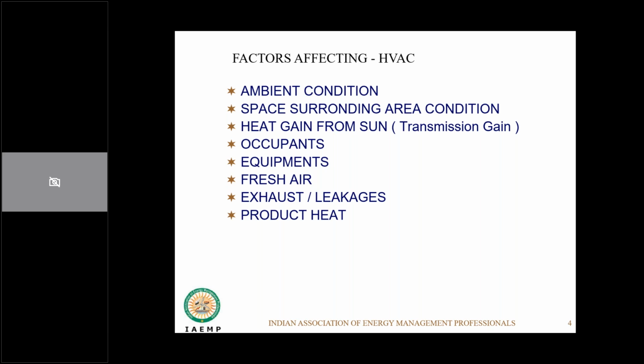This is also very important when you're doing cold storage, because if you have a product which is germinating, it generates a lot of heat, and you need to factor that in and maintain the right temperature in your cold storage. If you look into the cold storage of potato and onion, it's a very important factor, because if the temperatures go up, onion and potatoes start germinating, and then the product is lost and you have to throw it away. So this is where it's very important that you factor this heat in and give them the right temperature so that it is maintained in a pristine manner.